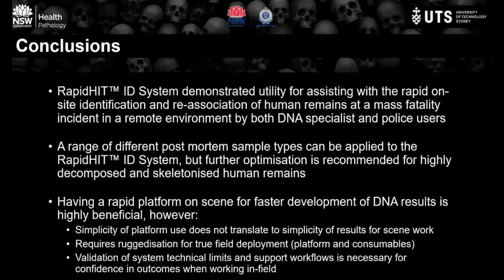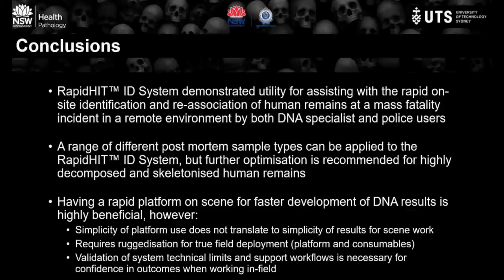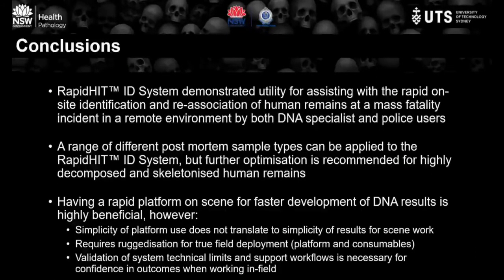In conclusion, the RapidHit ID system demonstrated its utility for assisting with rapid on-site identification and re-association of human remains at a mass fatality incident in a remote environment, by both DNA specialists and police users. A range of different postmortem sample types can be applied, but further optimisation is recommended for highly decomposed and skeletonised human remains. Definitely having a rapid platform on-scene for faster DNA results is highly beneficial. However, the simplicity of platform use does not translate to simplicity of results for scene work. Requires ruggedisation for true field deployment, and validation of system technical limits and support workflows is necessary for confidence in outcomes.